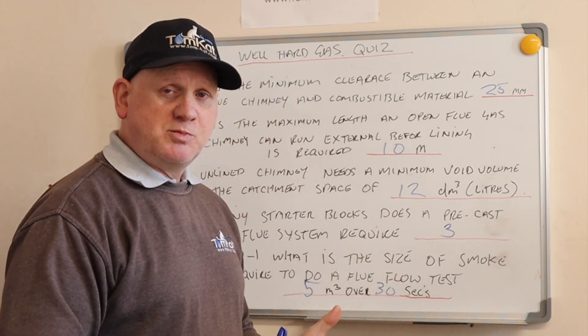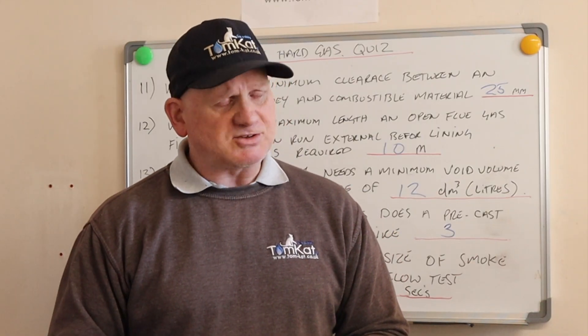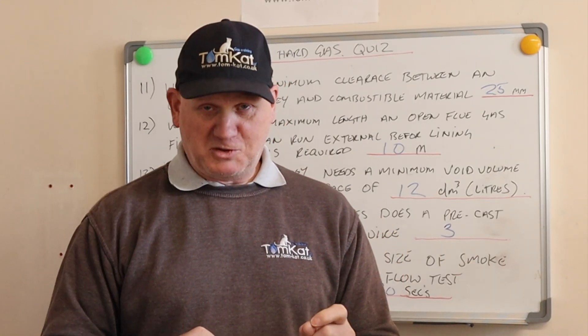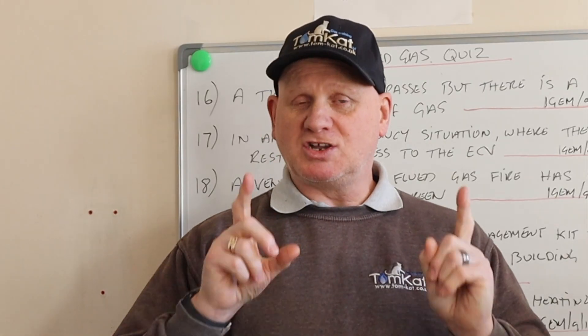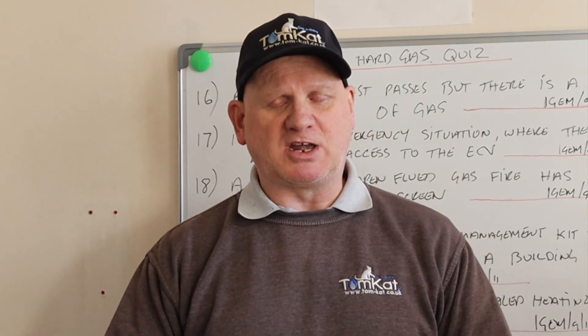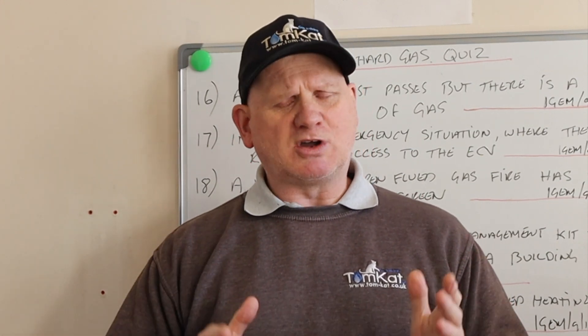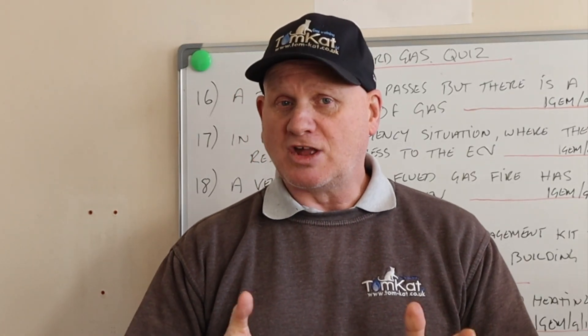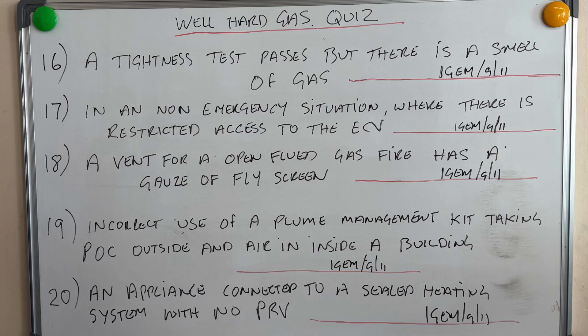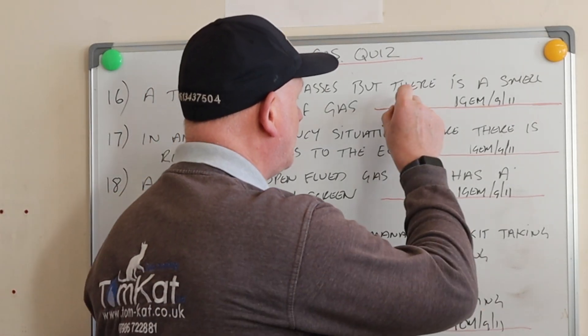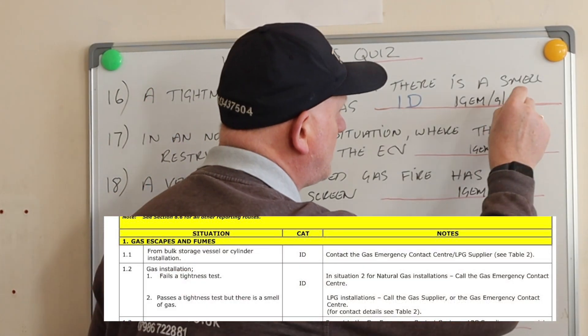Let me know your scores so far. Now for the final batch of five questions on unsafe situations — I'll also tell you where to find these in IGEM G11. Question sixteen: a tightness test passes but there is a smell of gas. Hopefully you said it is ID, and you can find it in IGEM G11 at section 1.2.